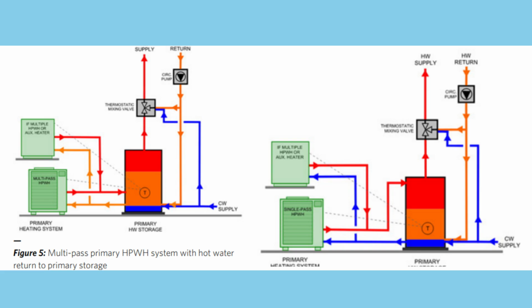Return to primary systems. Instead of using separate equipment, return water is directed into the primary system. In a multi-pass return to primary system, piping looks very similar to a gas boiler setup, which makes it familiar. But it comes with drawbacks: higher equipment capacity, slower recovery, and lower efficiency. In contrast, single-pass return to primary systems can work efficiently if the heat pumps are designed for it. They must handle return water at around 115 degrees, and controls must be carefully tuned. Manufacturers like Colmac and Nyle have models specifically designed for this configuration.